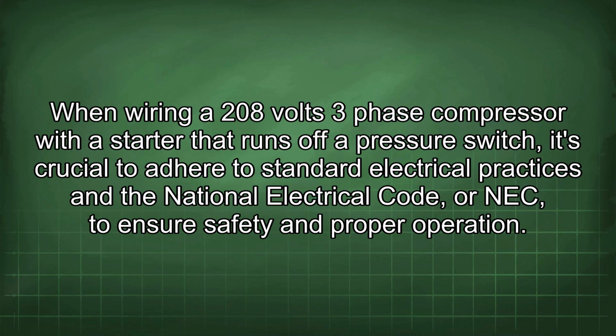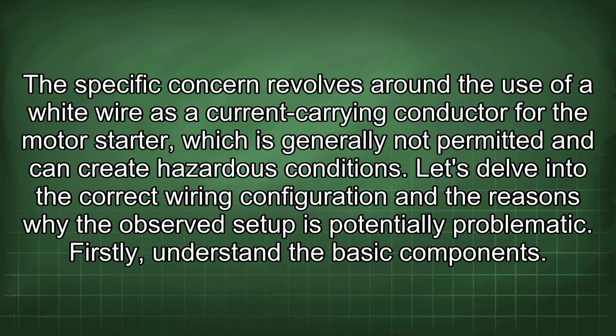When wiring a 208 volts three-phase compressor with a starter that runs off a pressure switch, it's crucial to adhere to standard electrical practices and the National Electrical Code, or NEC, to ensure safety and proper operation. The specific concern revolves around the use of a white wire as a current-carrying conductor for the motor starter, which is generally not permitted and can create hazardous conditions. Let's delve into the correct wiring configuration and the reasons why the observed setup is potentially problematic.